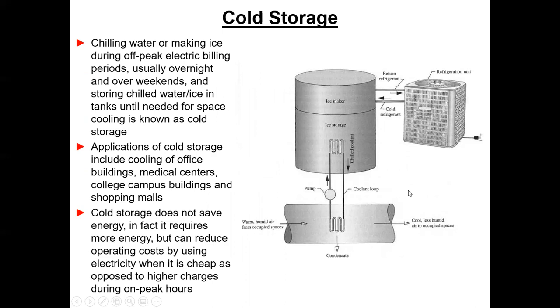This next topic relates to the electric rate file I sent you — I think I sent you one from Nashville. This is cold storage: chilling water or making ice during off-peak electric billing periods, usually overnight and over weekends, and storing chilled water or ice in tanks until it's needed for space cooling. Applications include cooling of office buildings, medical centers, college campus buildings, and shopping malls — any fairly large-scale operation that needs consistent air conditioning could be a candidate.